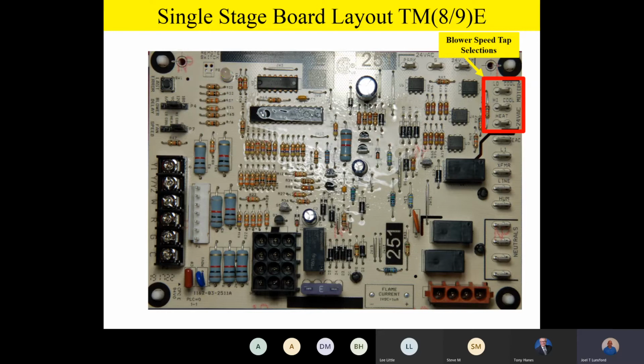And again, the way you find temperature rise, team, as a quick review, is you take your supply air temperature in the heating mode, you take your supply air temperature and your return air temperature, and you find the difference between those temperatures, and that's the temperature rise. And then the temperature rise range will be found on that data plate on the service panel.